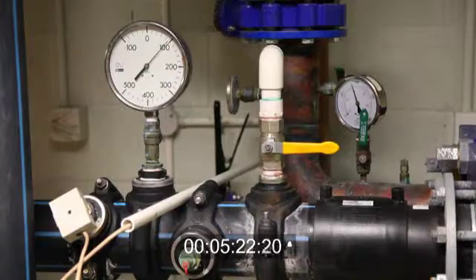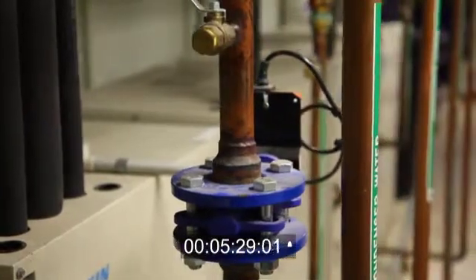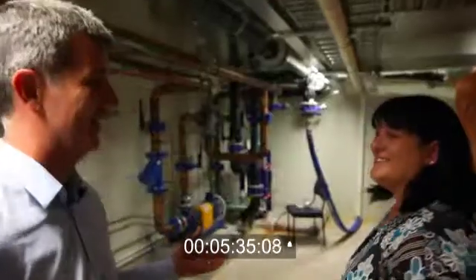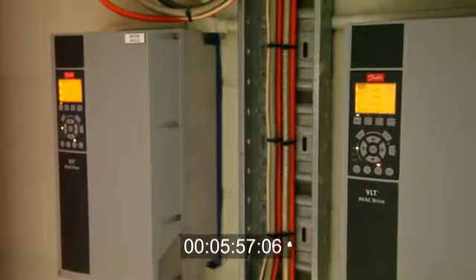So Trish, this is really the engine room of the whole place. It's literally the main plant area, and it's significantly servicing the geothermal system. The geothermal system is the one that extracts water out of the basin below the building, the artesian basin, pulling that relatively cool water up into the system, so it's pre-cooled effectively by the earth. That water's coming up through this system here, and then it's run through the plant and extracted at a much higher temperature, and put back into a thing called an injection bore, using that cool water to effectively supplement the energy costs of keeping the water cool, and then pumping that hot water back into the ground, and the ground will over time cool that down, so it mixes back into the system.